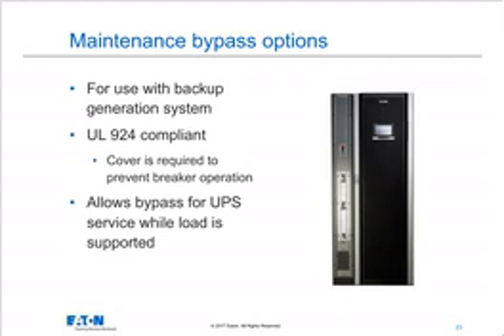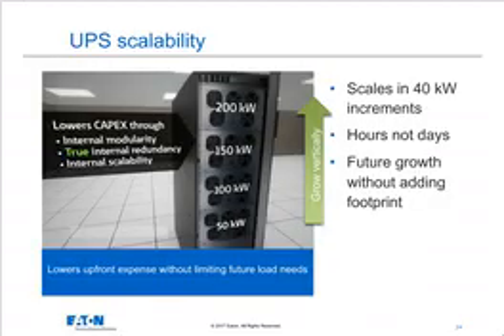Okay, in the next picture, we see a picture of the scalability I was talking about a couple of slides ago. This particular UPS is built on 50 kilowatt or 40 kilowatt blocks, depending on how much battery charge capacity we need. So the shelf, or the container itself, has 4 shelves, and I can populate with 1, 2, 3, or 4 power modules. So if all I need is 50 kilowatts on day 1, I can populate just 50, and I pay a lot less upfront, and the battery is going to be considerably smaller as well.